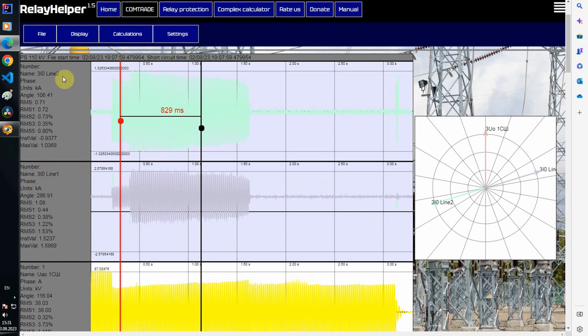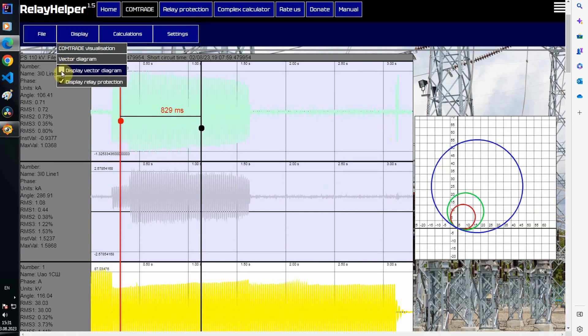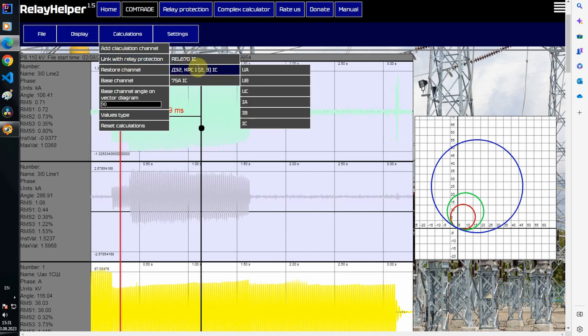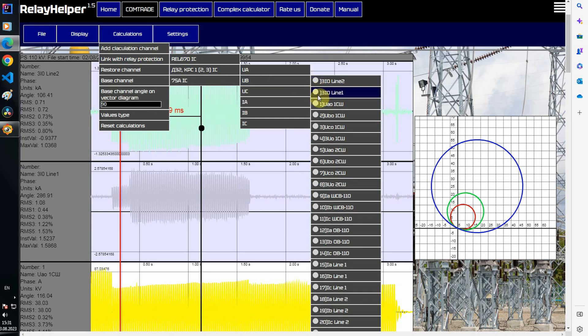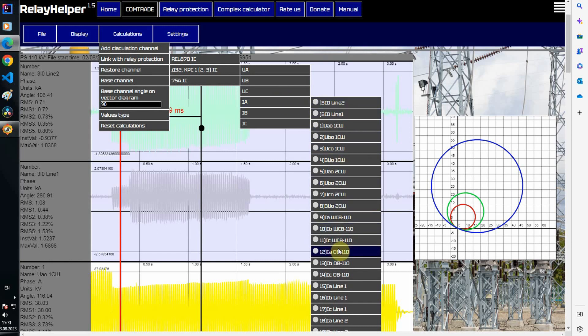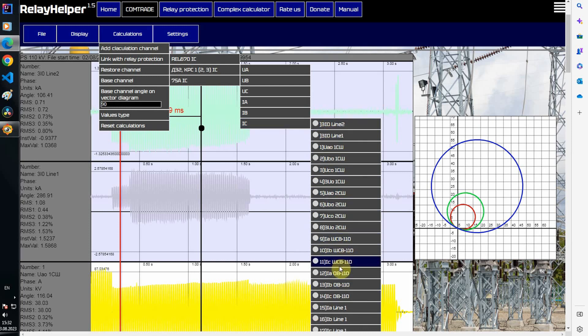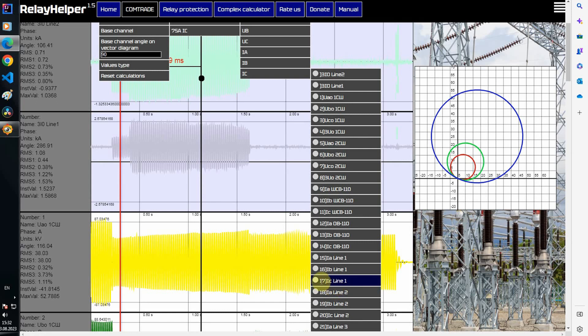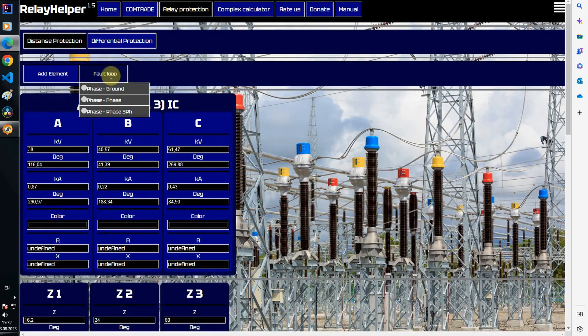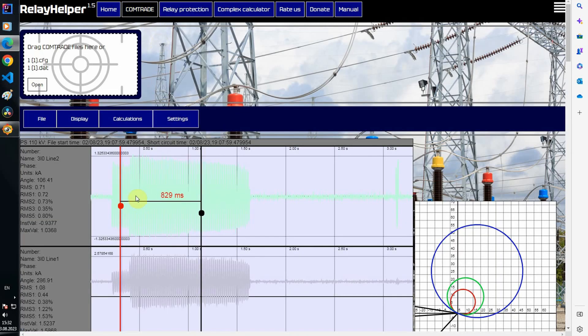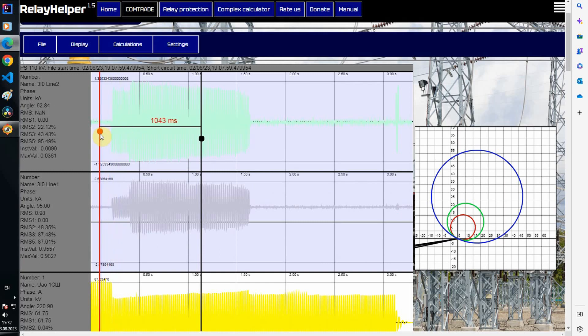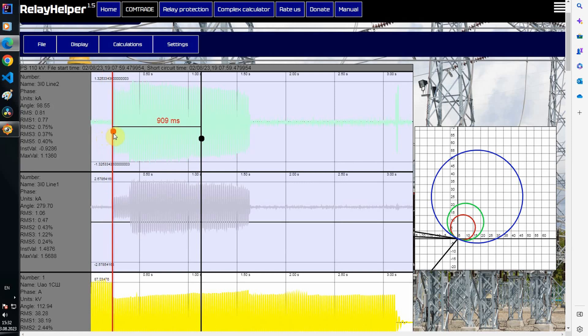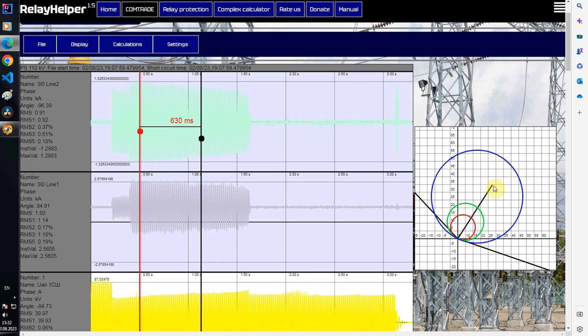Now let's add distance protection characteristics. I turn off the vector diagram linking comtrade file channels and a short circuit impedance calculator for the first line. I forgot to select the fault loop. Now it shows impedance vectors. Before fault, vectors looking in the reverse direction, also in the first section, and only here they move to the first quadrant impedance in the third zone.